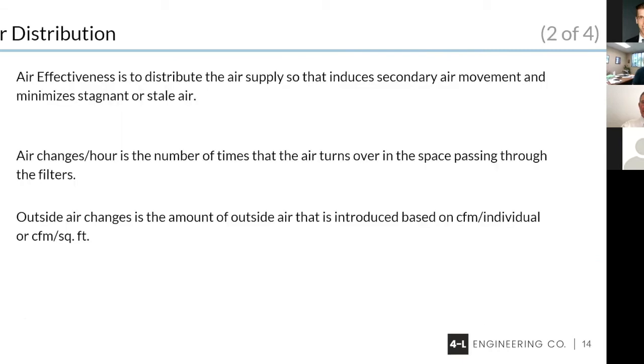The way we effectively move this air can improve the comfort level in a room. You'll be hearing us talk about air changes. Typically in a high-rise building in a unit, the air changes per hour will be somewhere around 6. We also talk about the outside air changes that we bring in. And typically we will be running somewhere around 1 air change of outside air. In the future, you're going to see these numbers tend to go up.